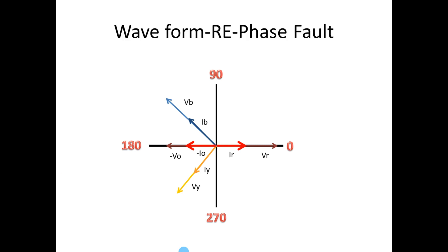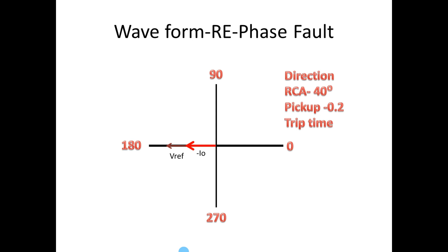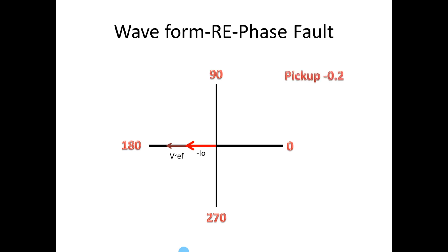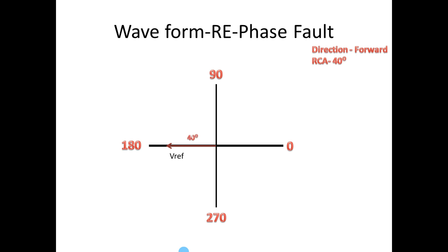Now we will see briefly the R phase earth fault. For this, V reference should be directly opposite to VR. For directional earth fault we need four important things: first, direction; second, RCA angle; third, pickup value; fourth, trip time. The most important is the pickup value — the fault current should be above the pickup value. The direction is forward, so V reference should be opposite to VR and RCA is 40 degrees. We take V reference as the reference point, make 40 degrees towards the clockwise direction and draw a line — this is the MTA.